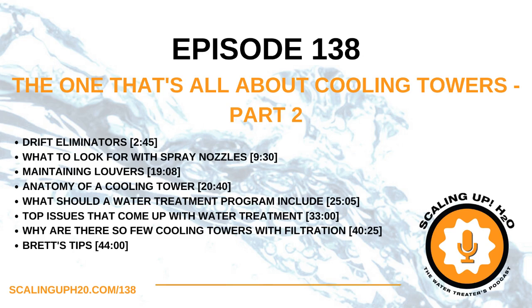I just can't get over the fact that people don't understand that chemistry cannot overcome a mechanical deficiency. If we don't have a filter to remove everything that tower - which you described as an air scrubber earlier - washes out of the incoming air, we can't expect good results from whatever water treatment program we're using, because we can't even get to the metal surface. I don't know what the answer is other than making sure we have dialogue with our end users about how important filtration is on these systems, because without it, we're fighting an uphill battle.